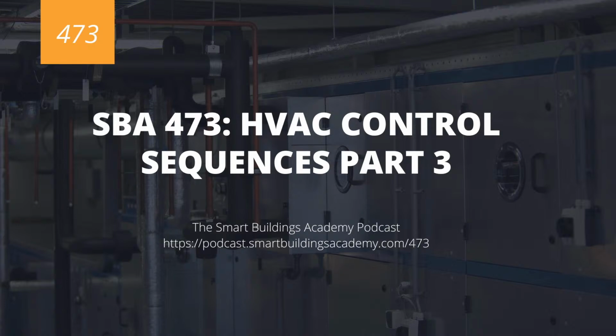Now, this discharge air pressure set point is anywhere between 1 to 3 inches water column. That's how we measure discharge air pressure. And how that discharge air pressure is affected is when VAV boxes downstream from this VAV air handling unit close or open up, that causes the discharge air pressure of the duct to change. And what will happen is that the air handler will be monitoring the discharge air pressure and discharge air pressure set point, and will vary the fan speed accordingly in order to basically provide the proper amount of air volume to these VAV units.